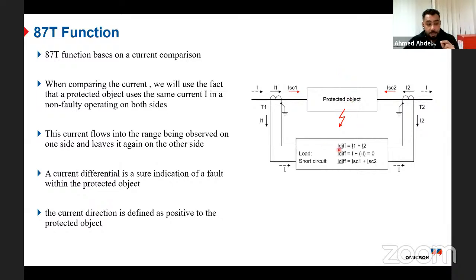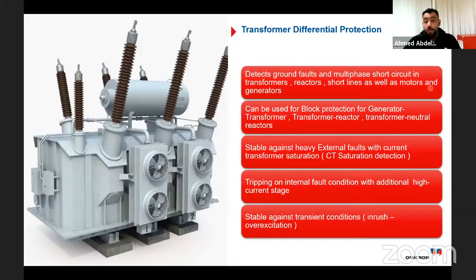So the protected element will differentiate between the current signal coming from CT T1 and the current signal coming from T2. If both of them are not equal to each other, it means I have an internal fault. If both of them are equal, it means that either I have an external fault behind this CT or I have a normal operation. This is the main idea about the 87T protection. Transformer differential should give me very, very selective protection and should work in this case to detect all ground faults and multiphase short circuits in case of transformer, generator, reactor, short lines, as well as motors.